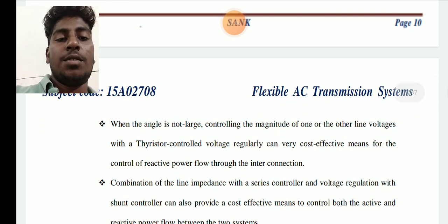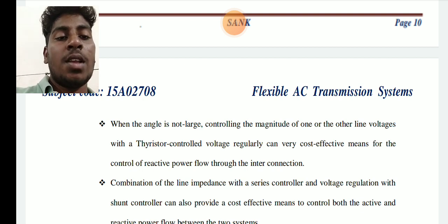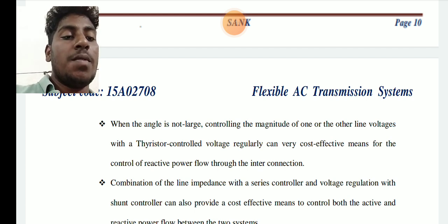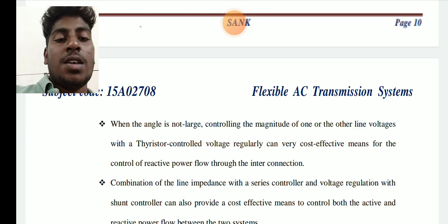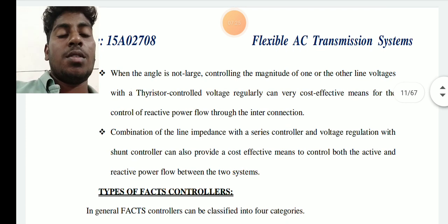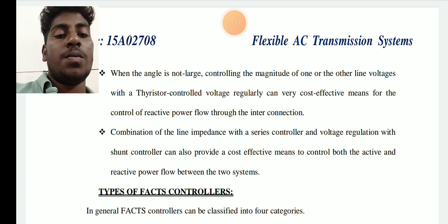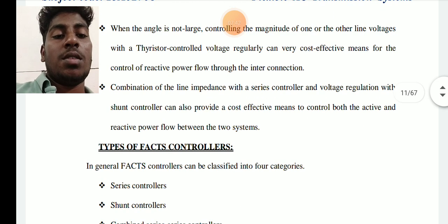So when the angle is not large, controlling the magnitude of one or the other line voltages with a thyristor controlled voltage regulator is a very cost effective means for controlling reactive power flow. The combination of series controller components with the voltage regulation of a shunt controller can also provide a cost effective means to control both active and reactive power flow between the two systems.